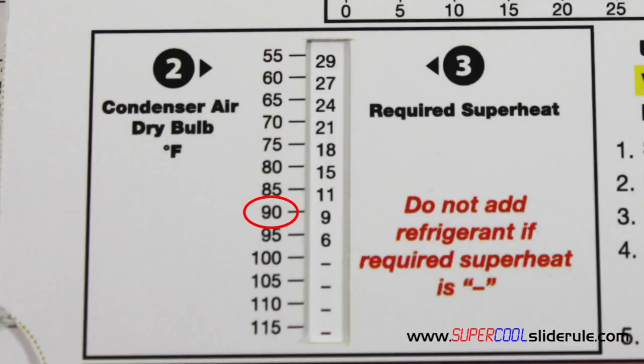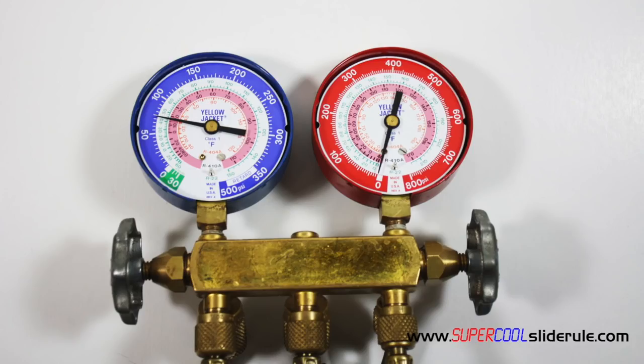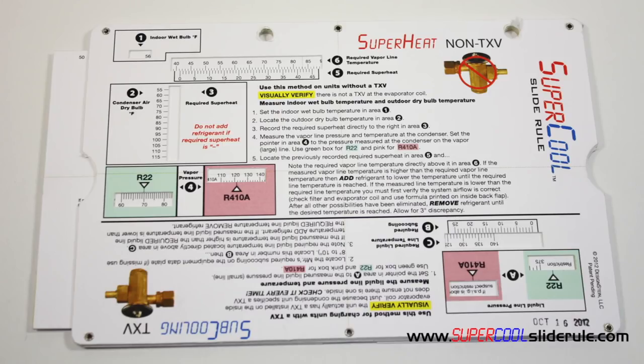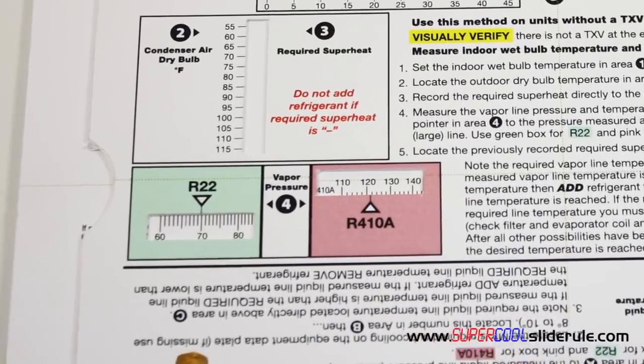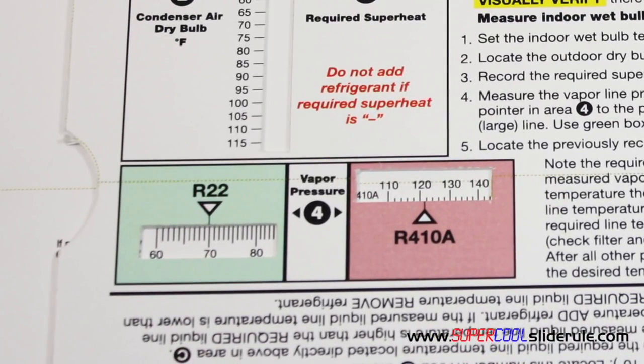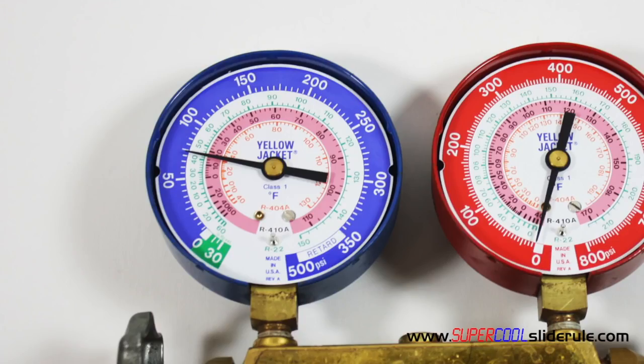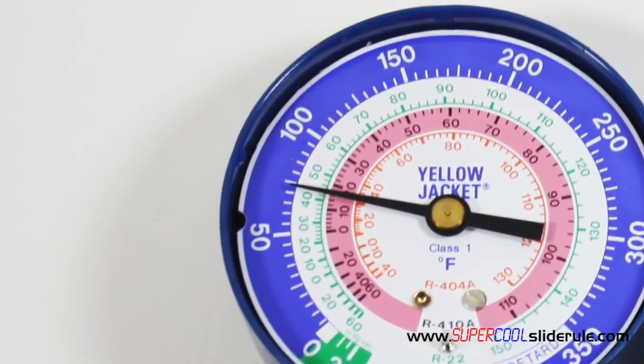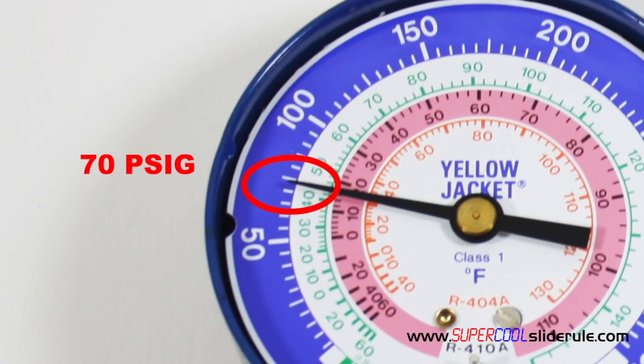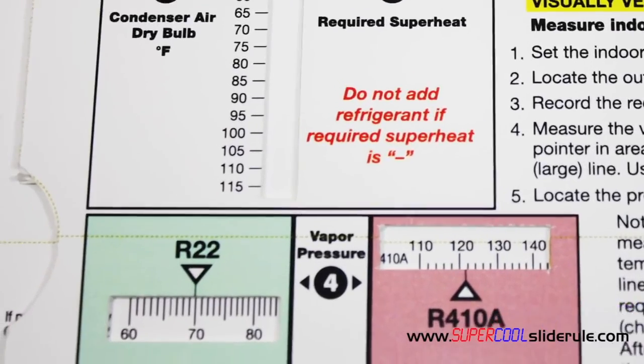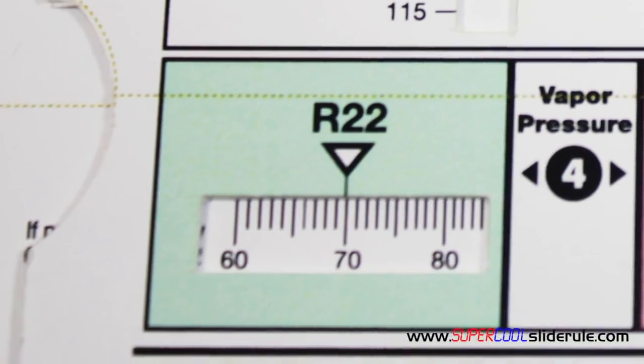Our next step is to measure the vapor line pressure. Now the vapor line is the larger of the two lines on a split unit, or the line labeled low side on a package unit. We set the pressure in window 4, use the green box for R22 or the pink box for R410A. In this example, our suction line pressure will be 70 psig. So we set 70 in the R22 box.